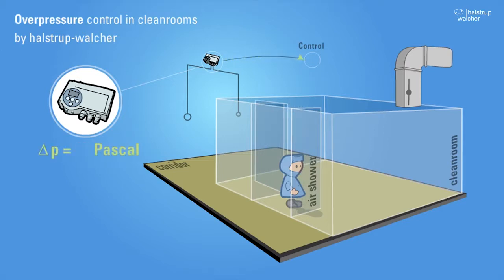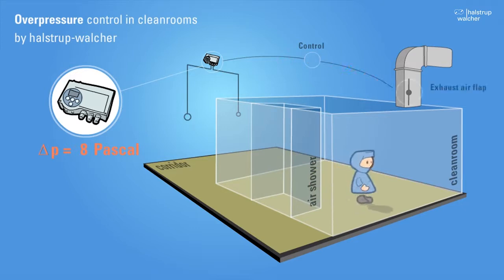If the room pressure falls from its normal level of 15 Pascal to a level below a threshold value, the control system responds by closing the exhaust air flap.